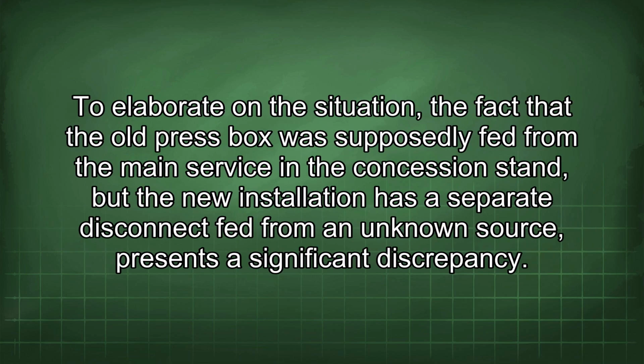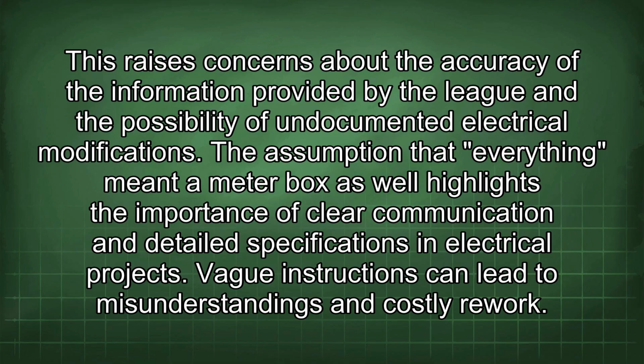To elaborate on this situation, the fact that the old press box was supposedly fed from the main service in the concession stand, but the new installation has a separate disconnect fed from an unknown source, presents a significant discrepancy. This raises concerns about the accuracy of the information provided by the league and the possibility of undocumented electrical modifications. The assumption that everything meant a meter box as well highlights the importance of clear communication and detailed specifications in electrical projects. Vague instructions can lead to misunderstandings and costly rework.